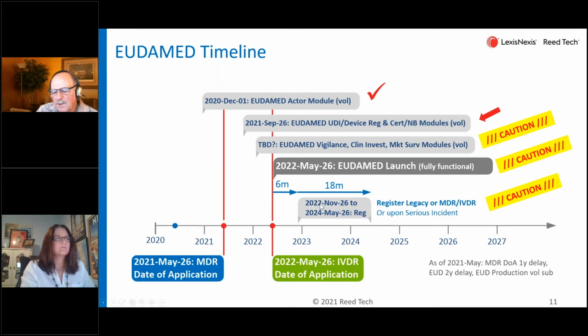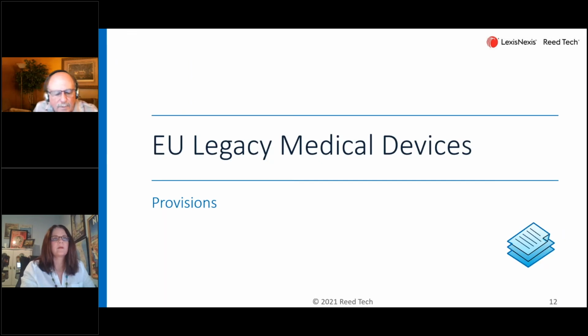The other thing I'll quickly mention is that this is a period of time for reporting, but in the event that your product has a serious incident, then you do have to report it very quickly. So almost immediately, 2, 10, or 15 days based on the severity. So I think that completes the first definition, Angela?